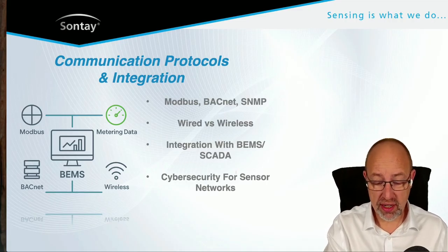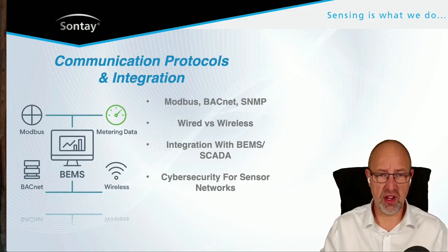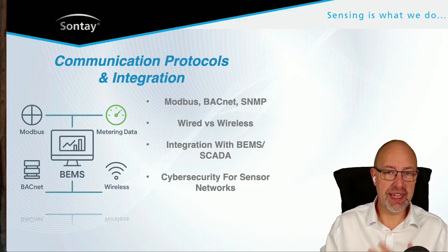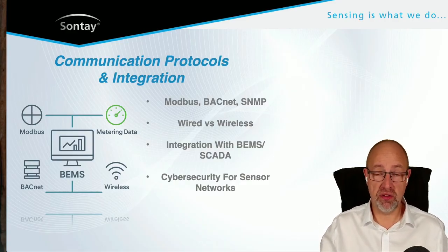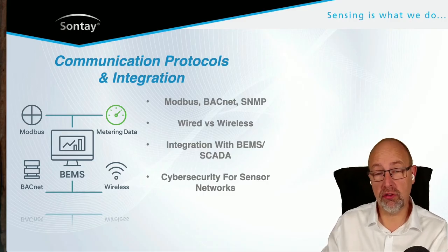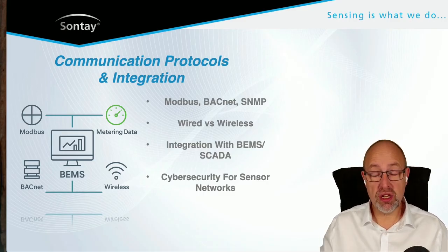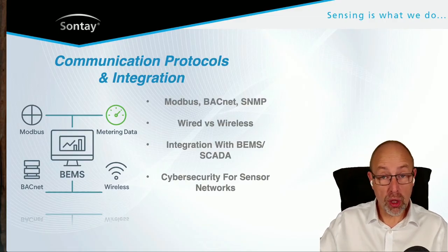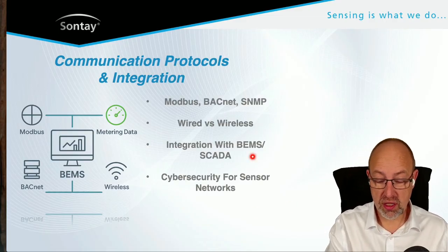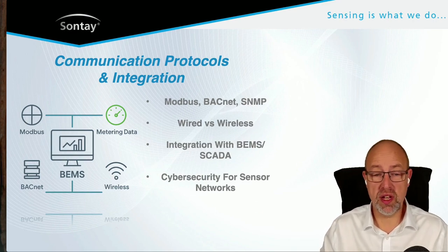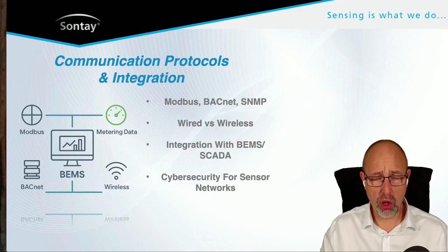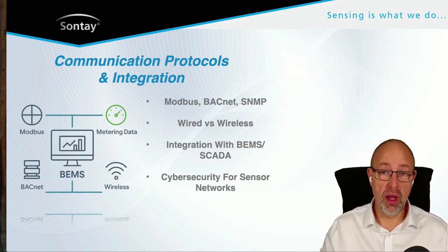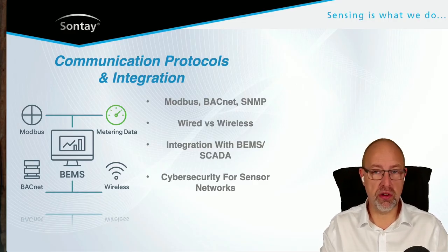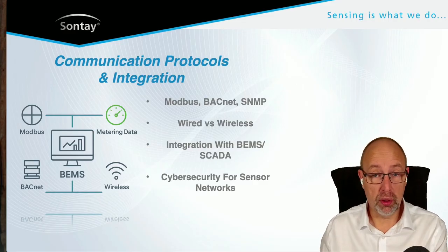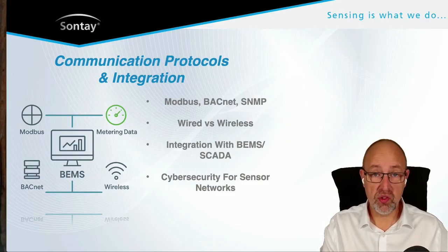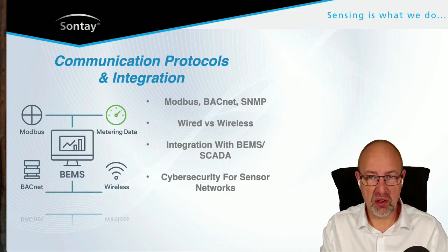And all of this, if we're integrating with a BEMS or a SCADA, or what we would refer to as an ISN, an integrated services network, where it's physically segregated from all of the data networks, then of course we have segregation. We don't have the security issues. But if we are integrating with cloud services, with components which sit on the data network, then we do need to very much consider the cybersecurity of those sensor networks as well. And it's one of the reasons a lot of data centers actually prefer more traditional sensors where you've got thermistors and 0 to 10 volt signals coming back to more manageable equipment, rather than using these wireless and wired bus technologies.